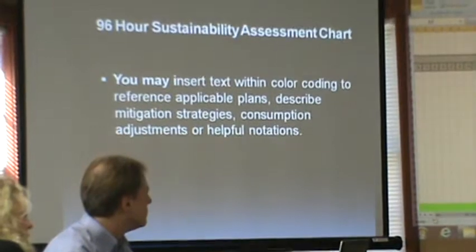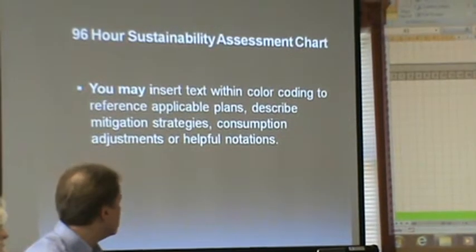At 84 hours, normal and emergency operations are significantly impacted. All internal resources and strategies to mitigate the impact have been depleted. We're basing this on the 96 hours of the Joint Commission standard of standing alone. But a hospital's not tied to that for use of this. If you want to make an assumption that your bulk oxygen supplier is across the street, and you know that regardless of the event, even though it's snowing heavily, you can still get the bulk oxygen, so you're going to make a different determination here, that's fine.